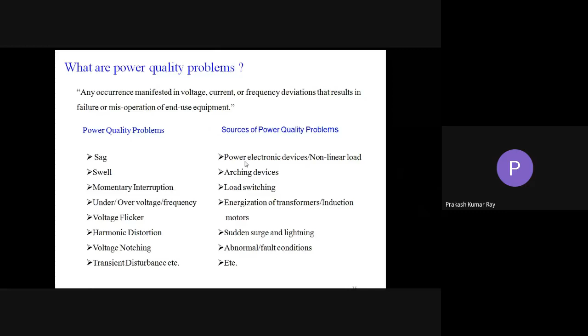These are the sources of power quality problems. There may be power electronics. Usually the nonlinear load is the main culprit that is creating a lot of harmonics in the system. Then arcing devices, load switching, energization of transformers or induction machines, sudden surge and lightning, abnormal fault conditions, and many other operational issues are creating a lot of power quality problems that affect the performance of the power system.